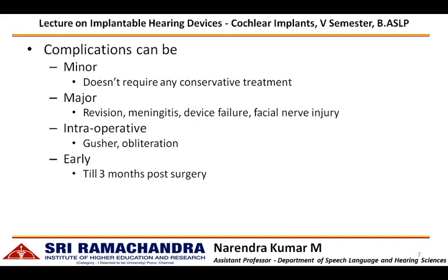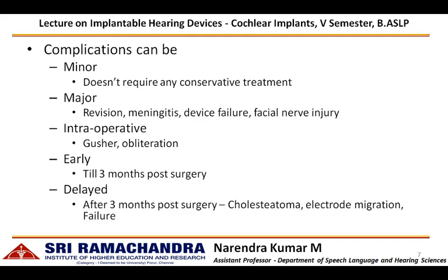Complications can occur early, up to 3 months post-surgery, or in a delayed manner after 3 months post-surgery. These delayed complications include cholesteatoma formation in the middle ear, electrode migration from the cochlea, and failure of the device.